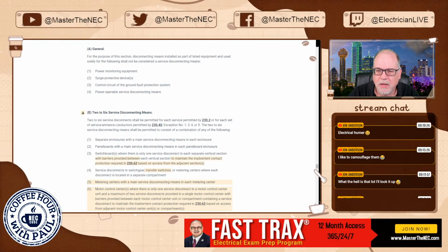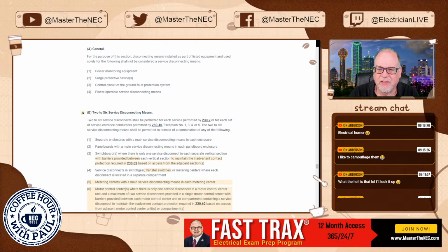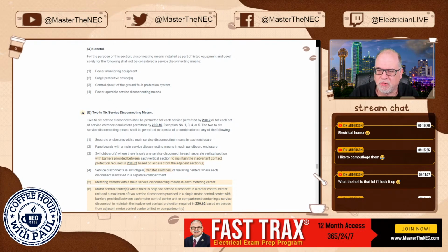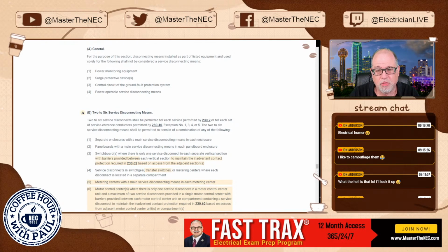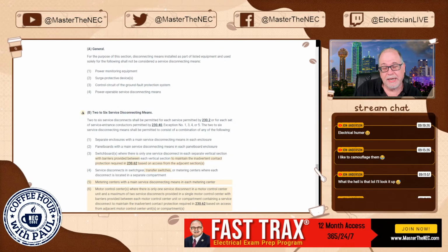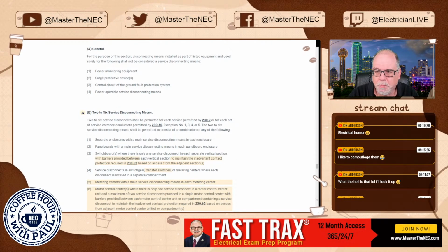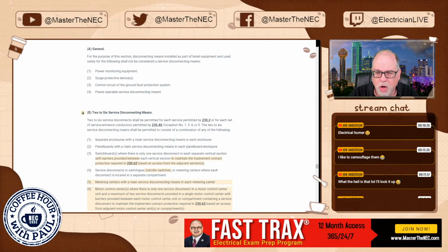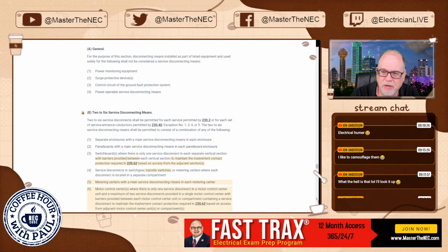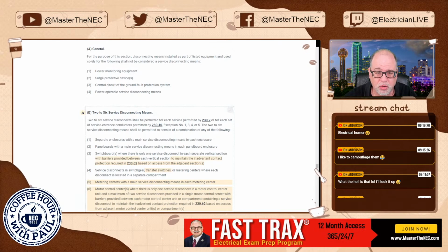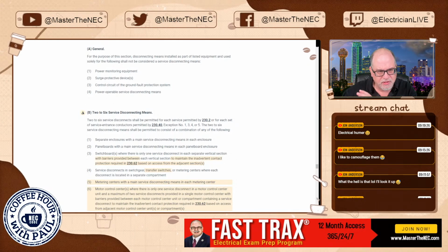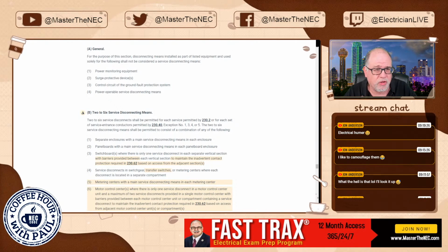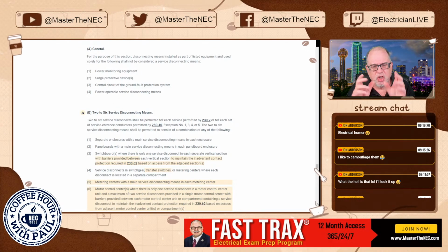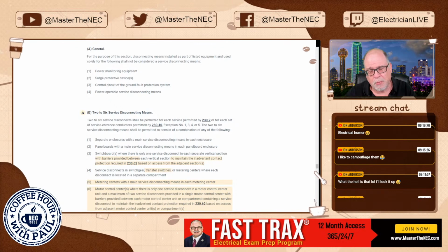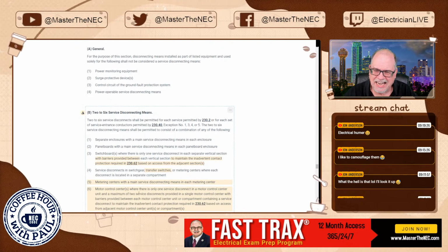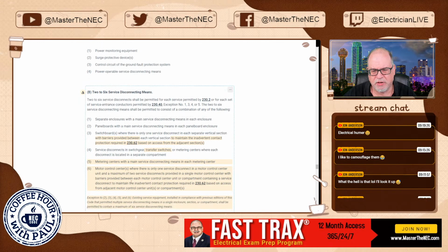Also, 230.71(B)(6) was added for motor control centers used as service equipment. That is to limit the equipment to a maximum of what? Two service disconnects per single motor control center, with barriers required between each unit or compartment. So if you have a motor control center, you have the two to six service disconnect rule. But if it's a motor control center that's being used as service equipment, you're going to be limited to two, and they're going to be in separate compartments. So we just added some additional rules in here for you to be aware of.